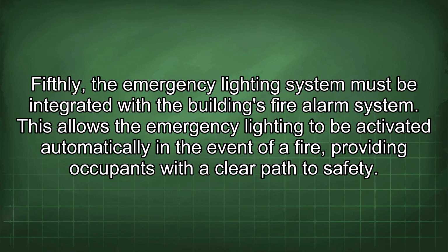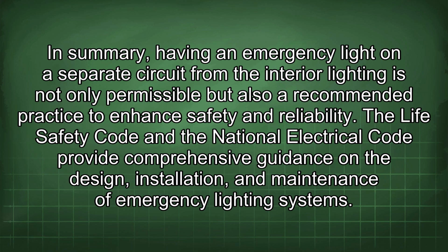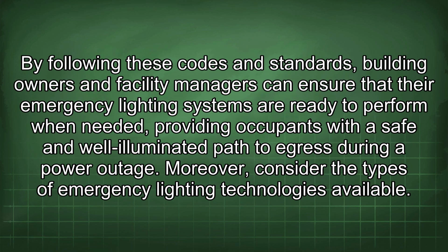In summary, having an emergency light on a separate circuit from the interior lighting is not only permissible but also a recommended practice to enhance safety and reliability. The Life Safety Code and the National Electrical Code provide comprehensive guidance on the design, installation, and maintenance of emergency lighting systems. By following these codes and standards, building owners and facility managers can ensure that their emergency lighting systems are ready to perform when needed, providing occupants with a safe and well-illuminated path to egress during a power outage.